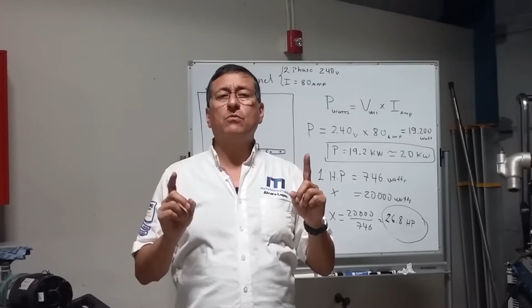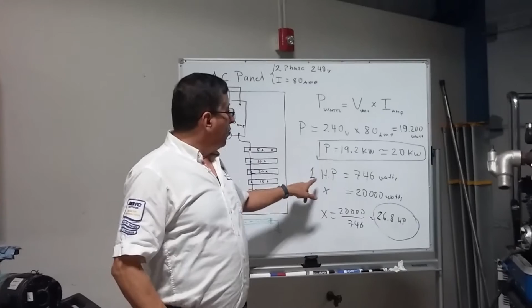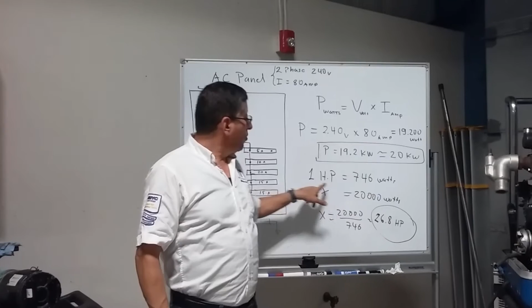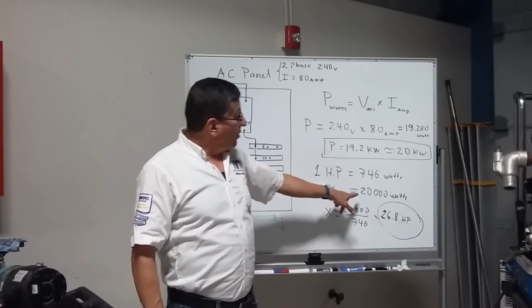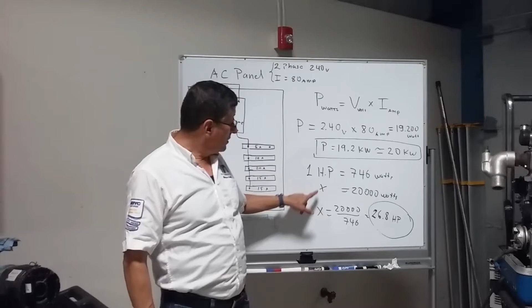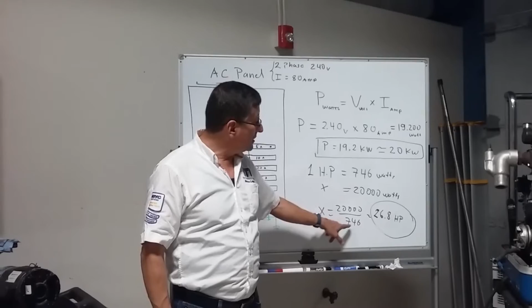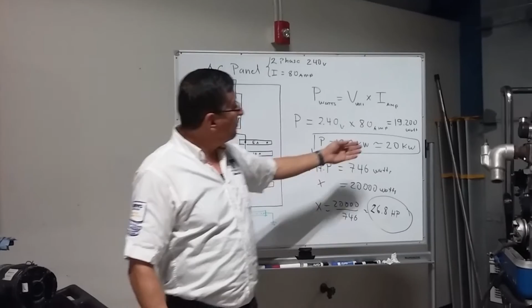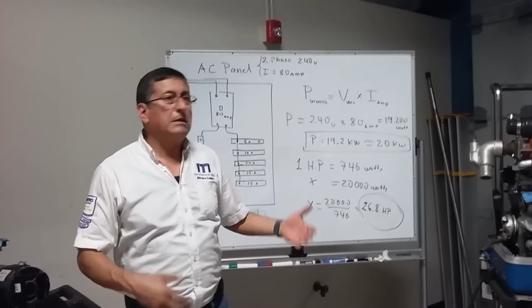In order to calculate the capacity of the engine, you need to use the magic formula to convert mechanical power into electrical power. The formula is 1 horsepower is equivalent to 746 watts. 1 horsepower is equal to 746 watts. Okay, if I have 20,000 watts, how many horsepower is that? It's simple. The horsepower is basically 20,000 divided by 746. This is 26.8 horsepower. In this particular example, for that generator, you need a minimum of 27 horsepower. I need to replace the engine with another engine of 27 horsepower.